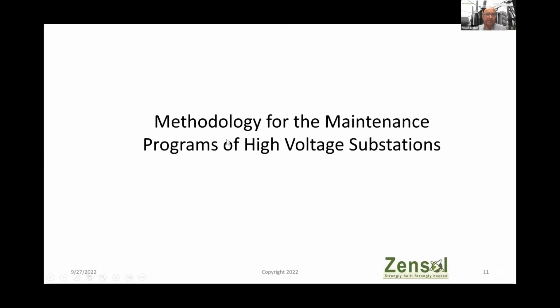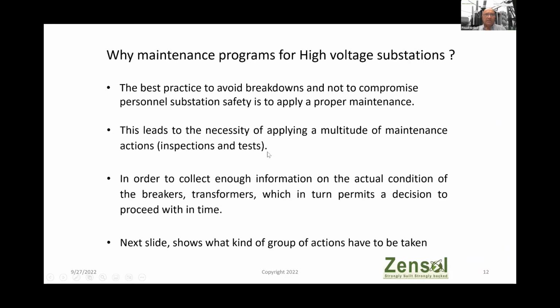So here is the methodology for maintenance programs of high voltage substations. Why maintenance? The best practice to avoid breakdown and not compromise personal and substation safety is to apply proper maintenance. This leads to the necessity of applying a multitude of maintenance actions, based on inspections and tests, in order to collect enough information on the actual condition of the breakers and transformers. With this information, we can take a decision to proceed in time.